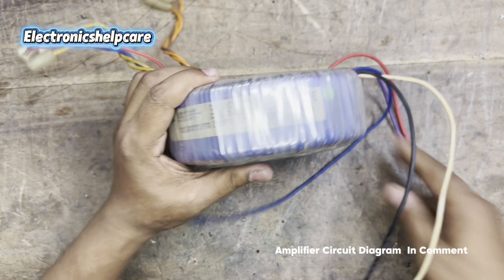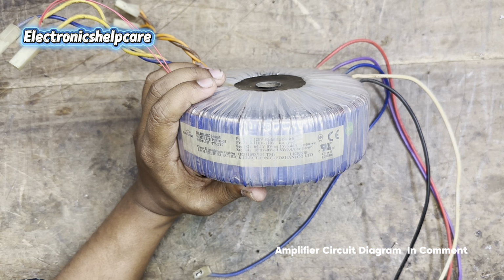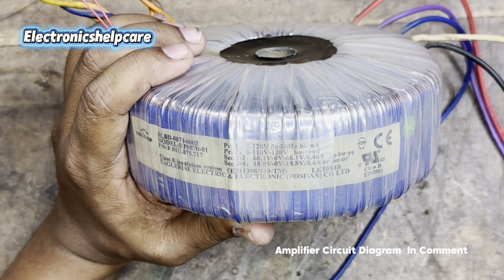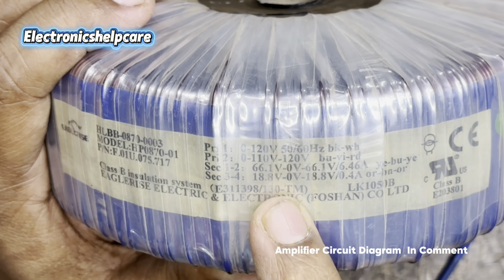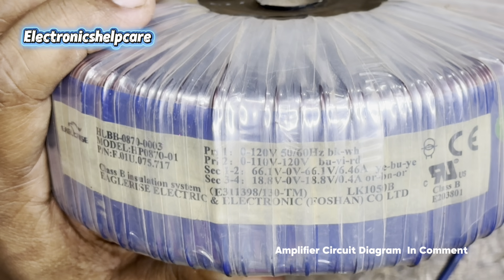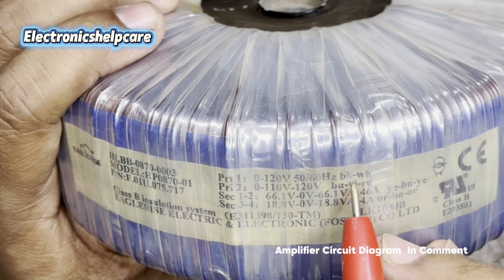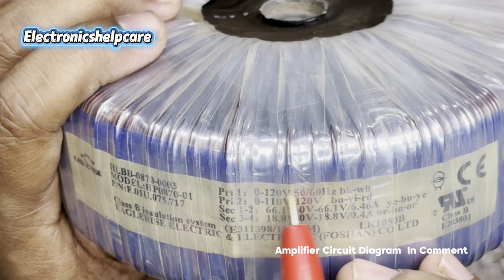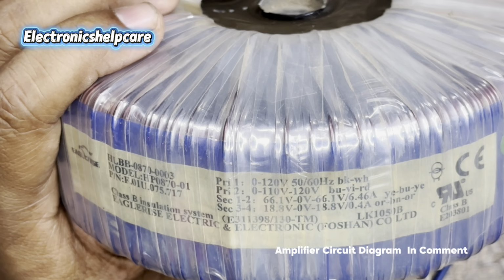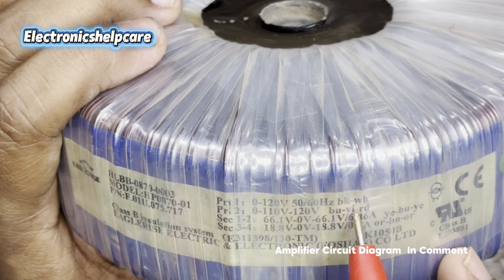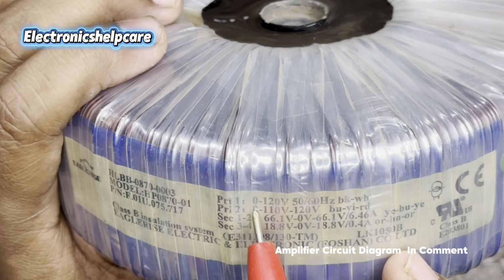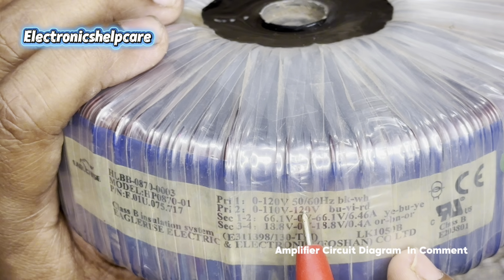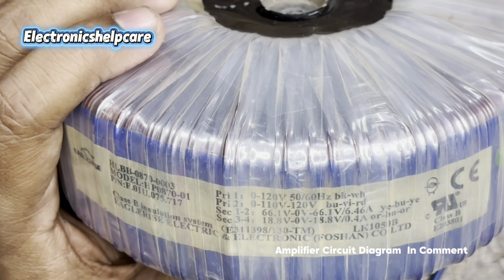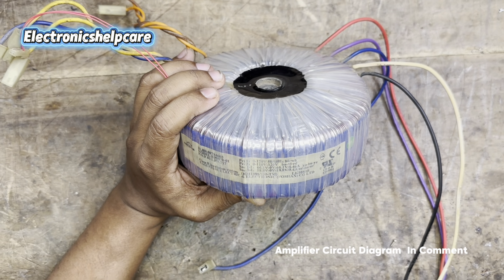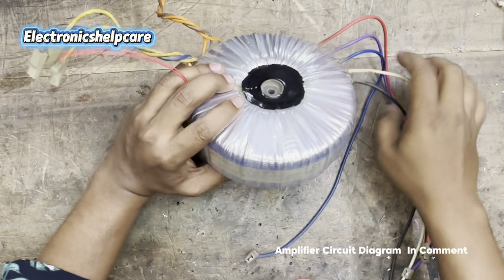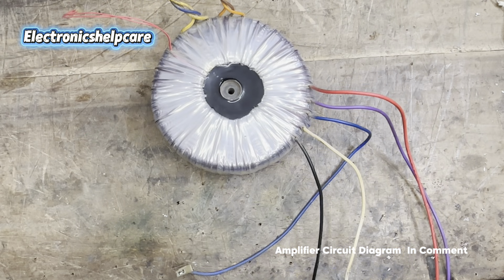Okay, I am going to check which wire is for primary. Look, here we can see black and white is 120 voltage, 0 to 120, and blue, red and violet is 0, 110, 120. Blue is 0, violet is 110, and red is 120. Now our primary voltage is 220, so we have to series the sections.